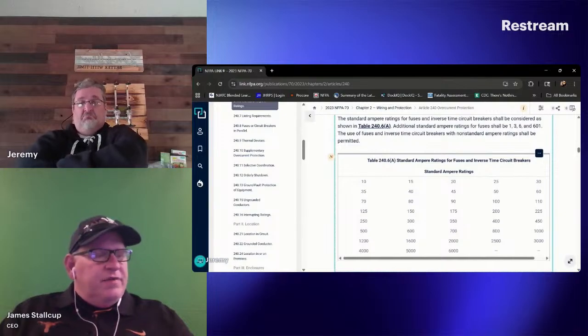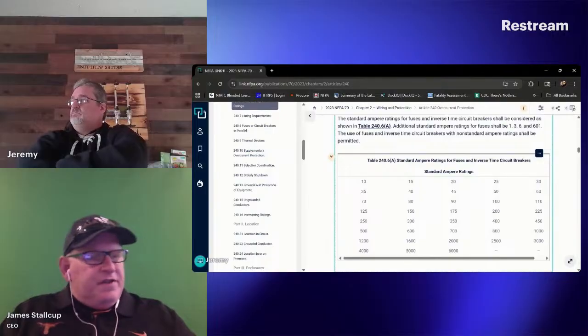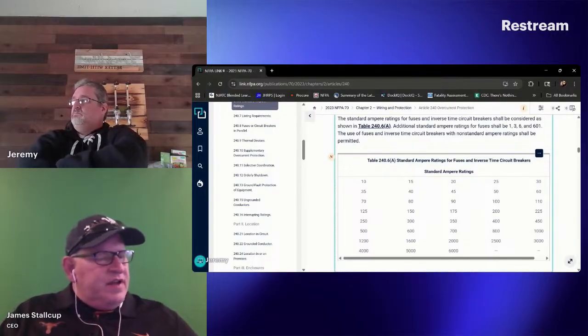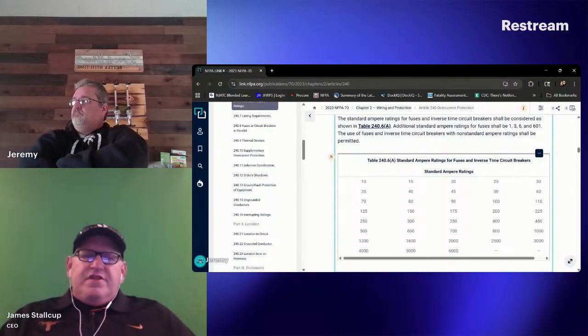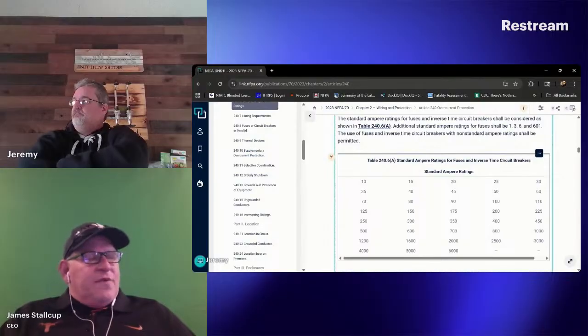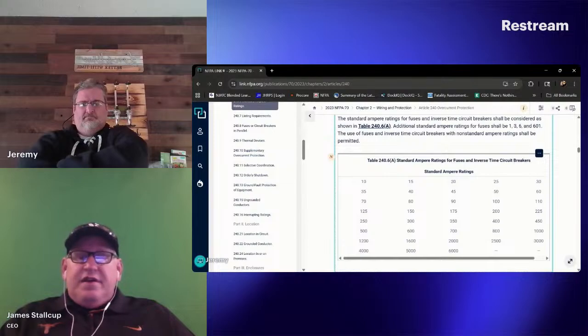You took a 310, that's 310 amps times 5, which gives you 1550. If I take my calculated load, which was 1505 amps, you've got 45 amps there, and I'll guarantee you it would probably be a lot less than that, but I'll guarantee you've got diversity in there, that nothing is operating at 1500 amps total through that whole service at full load the whole time.